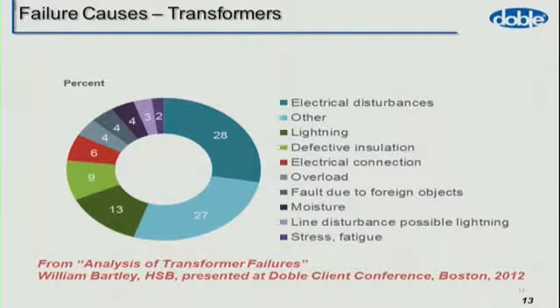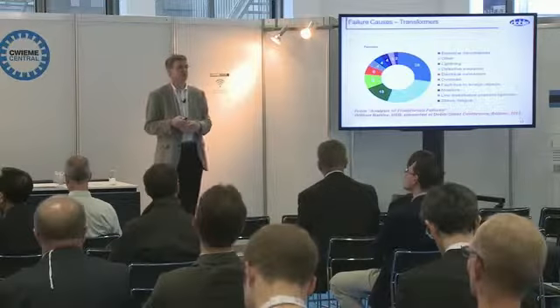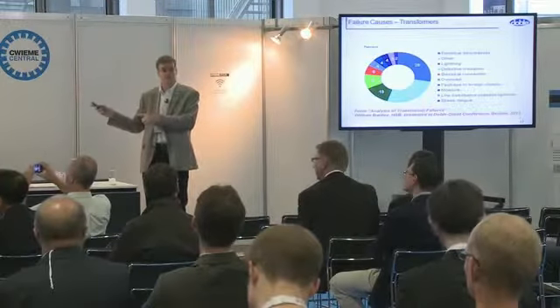Look at the top 3 causes: electrical disturbances outside of the transformer, and other causes outside the transformer like lightning. Those 3 main causes account for two-thirds of failures, and they're all external to the transformer. It does get complicated because the older a transformer is, the less likely it is, due to aging, to withstand an external fault. But two-thirds of the problems are externally caused - vandalism, lightning, other sources. Our intelligent condition monitoring is not necessarily going to address those causes.